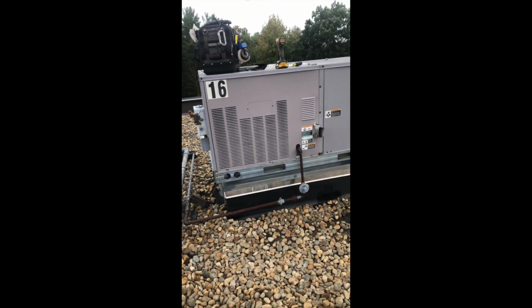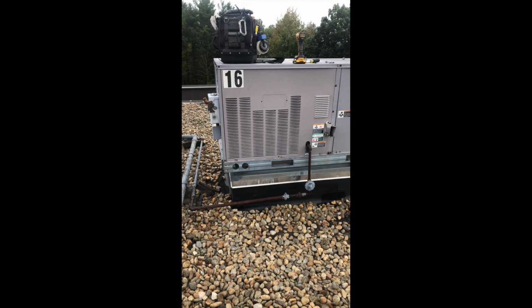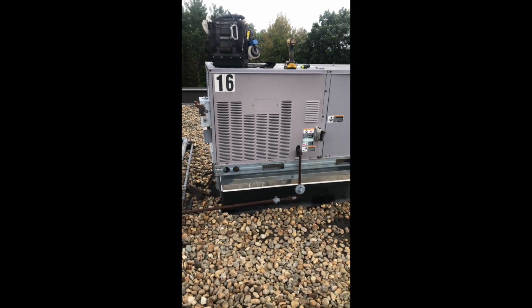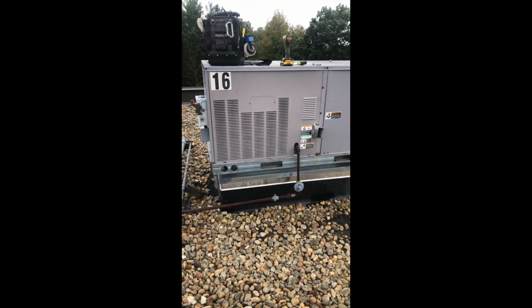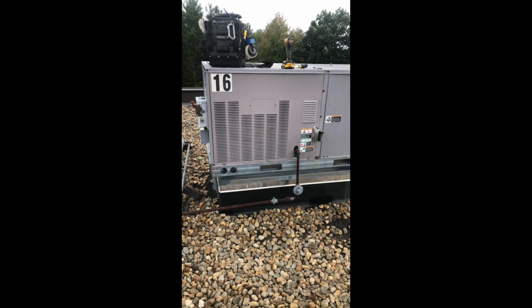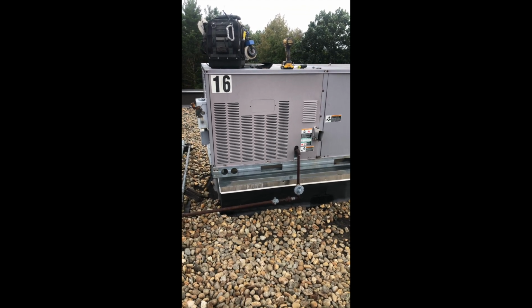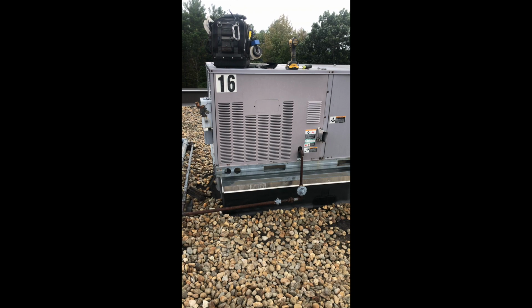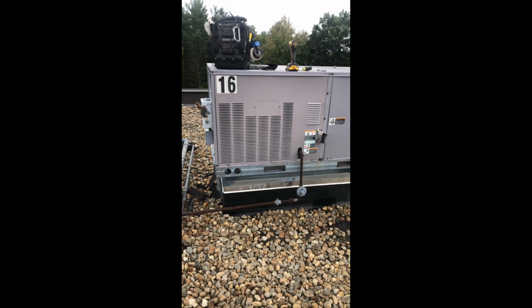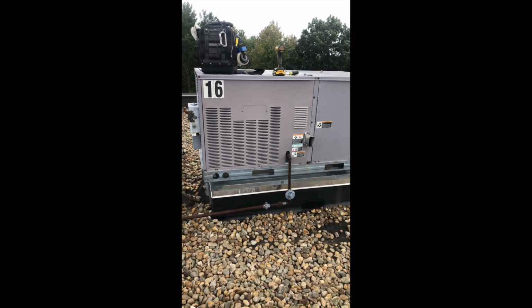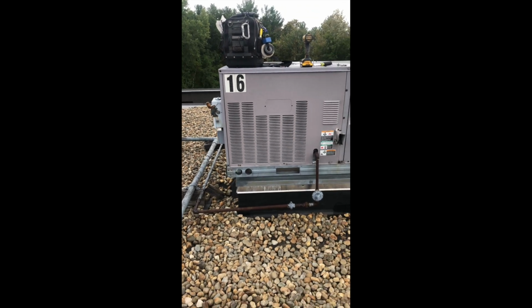When it's out on a rollout switch, the first thing you want to look for is a big enough hole to push that flame out of the heat exchanger, and sure enough, like I showed you, a big gap, a couple of Mariana's trenches in the heat exchanger.